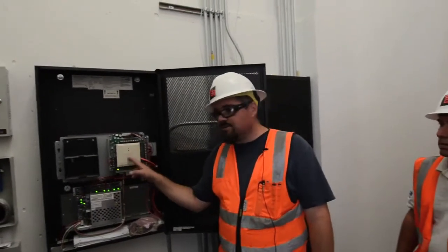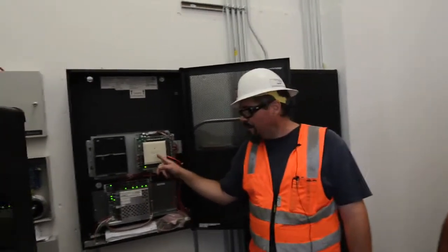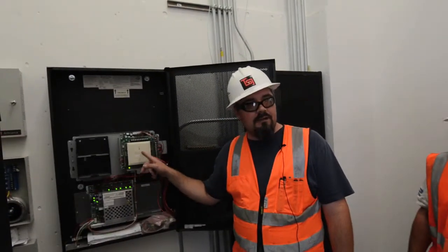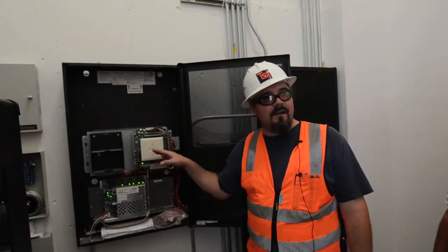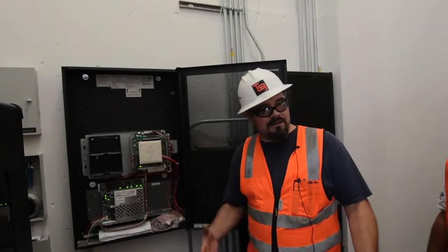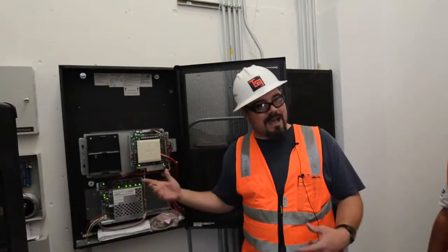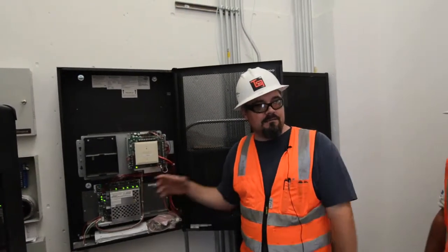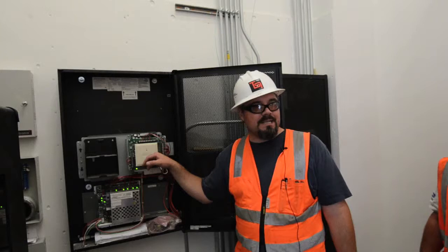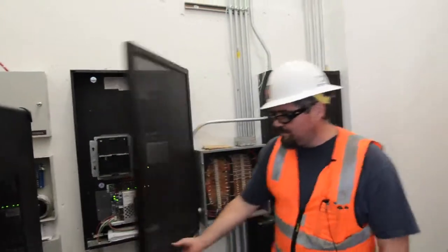This module here is for this power supply. So if there is an issue with this power, it's going to report off this monitor module, and it will report to the fire panel and will say this number in this room at this power supply has an issue. So it makes it easier versus having one wire connect them all, and then something happens, you'd have to check all of them. This enables you just to go to one location where it might be having a problem. So that's my transponder for the power supplies for the CNG.